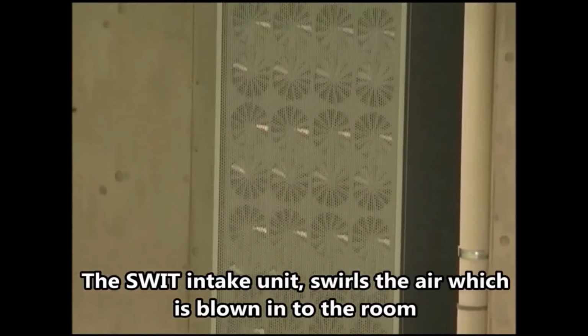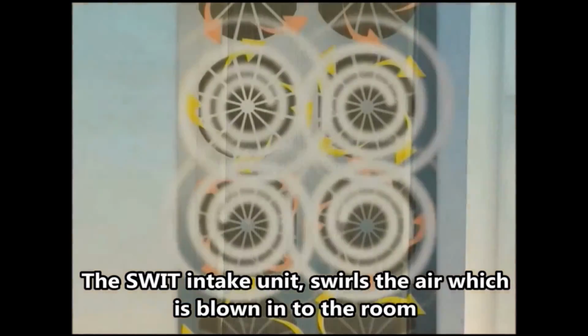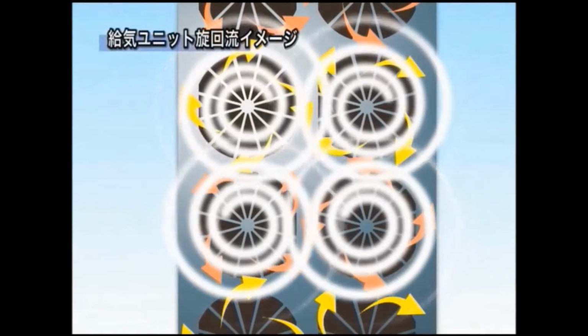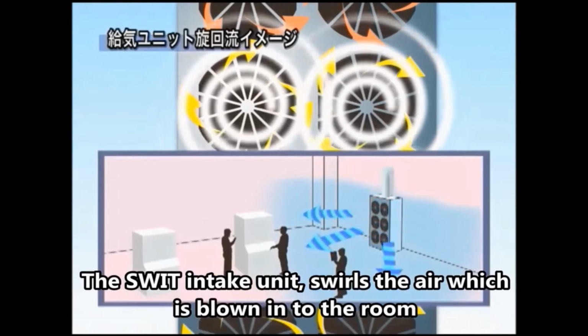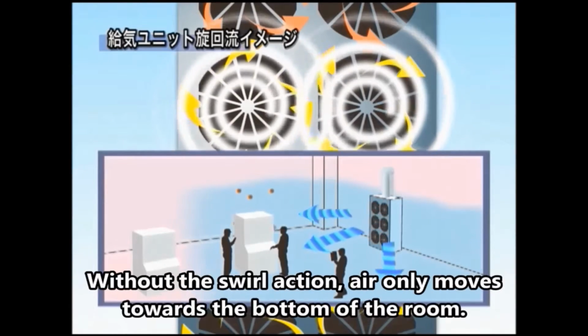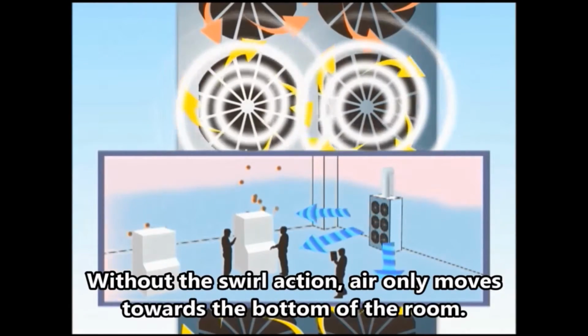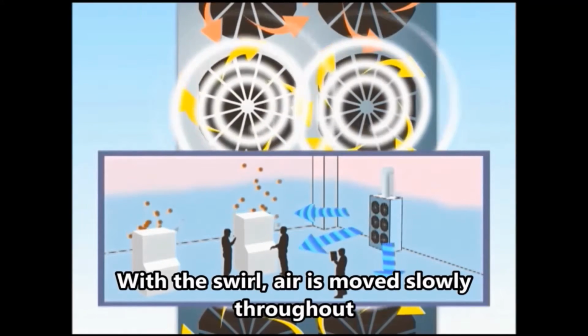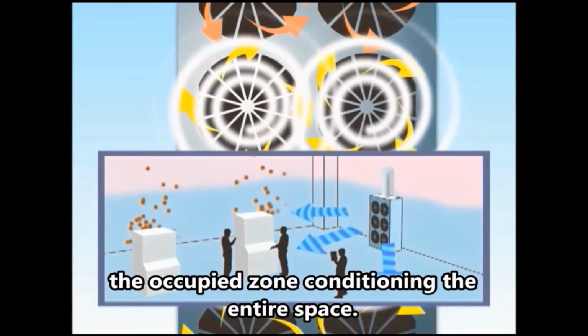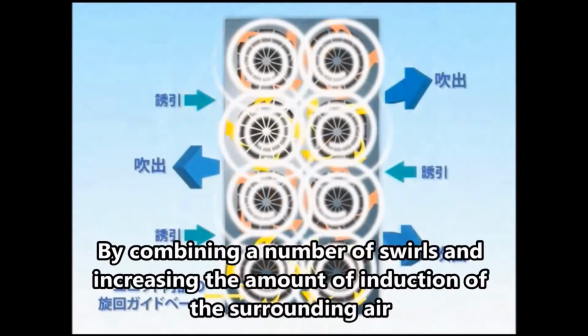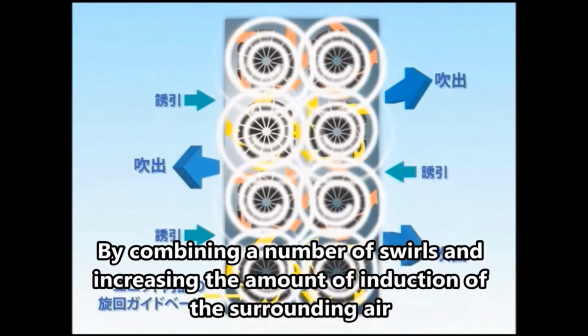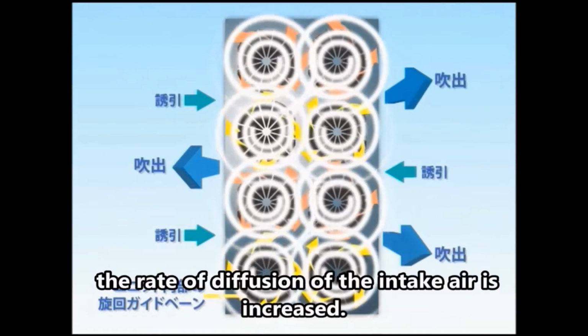The Swit intake unit swirls the air which is blown into the room. Without the swirl action, air only moves towards the bottom of the room. With the swirl, air is moved slowly throughout the occupied zone, conditioning the entire space. By combining a number of swirls and increasing the amount of inductions of the surrounding air, the rate of diffusion of the intake air is increased.